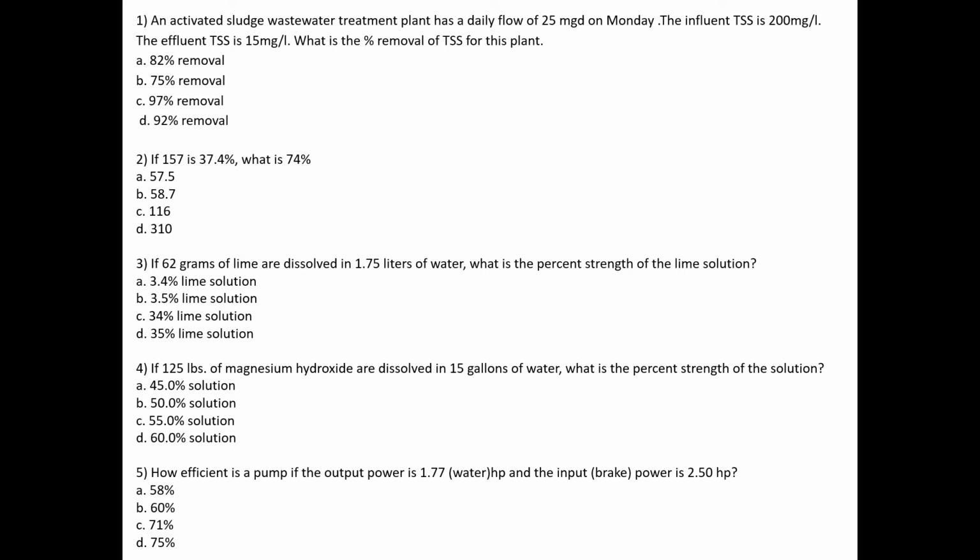So to move a certain amount of flow, a certain distance with a certain amount of resistance, the formula for the water horsepower is GPM, gallons per minute, multiplied by the total dynamic head, and then divided by 3,960. Where did they get that number?